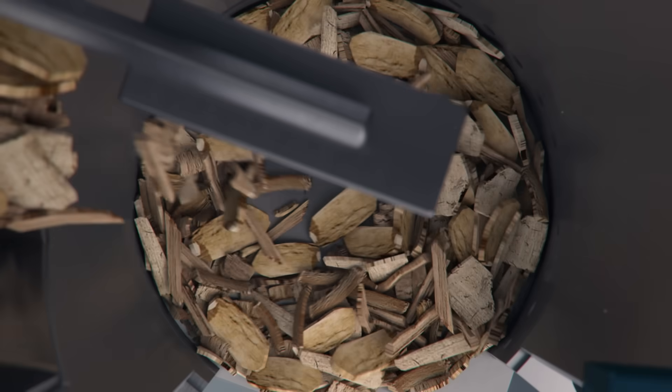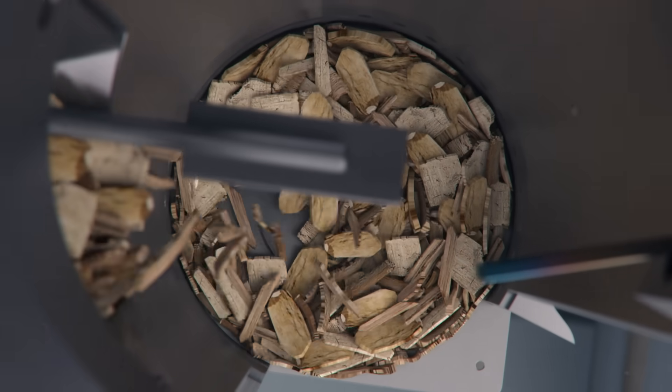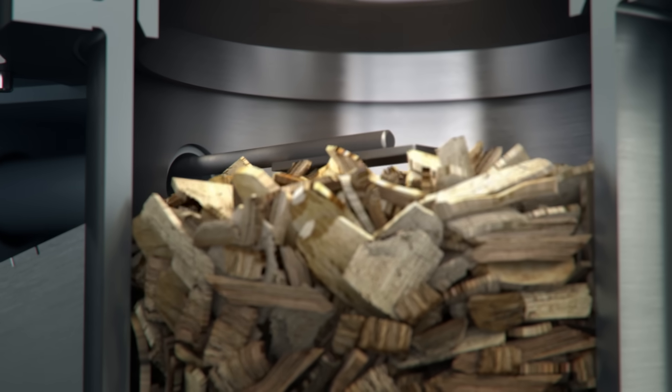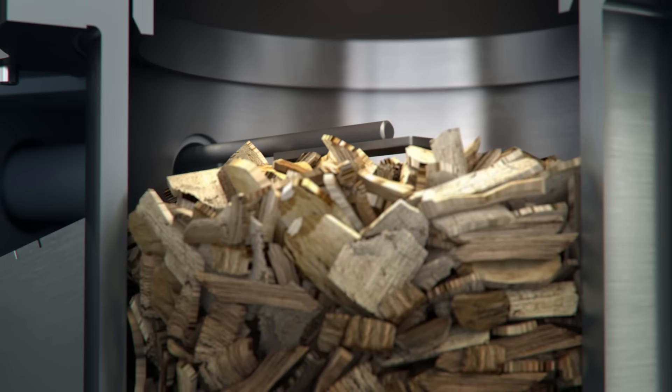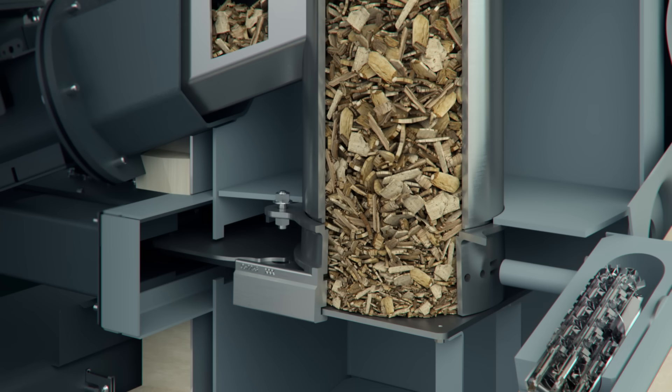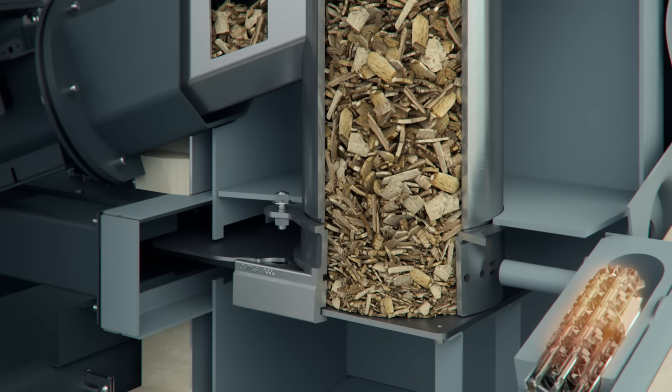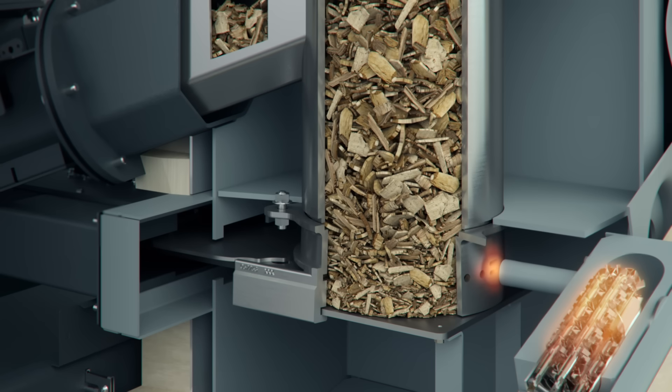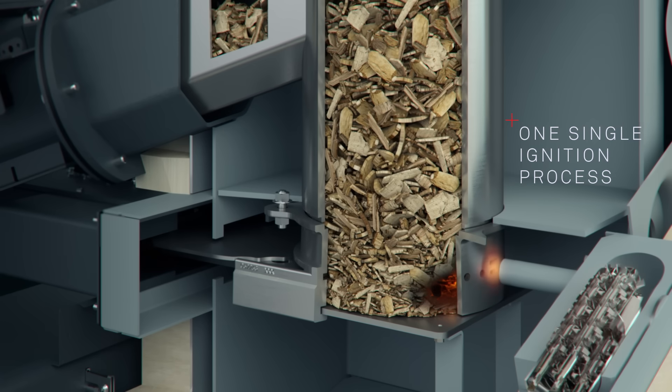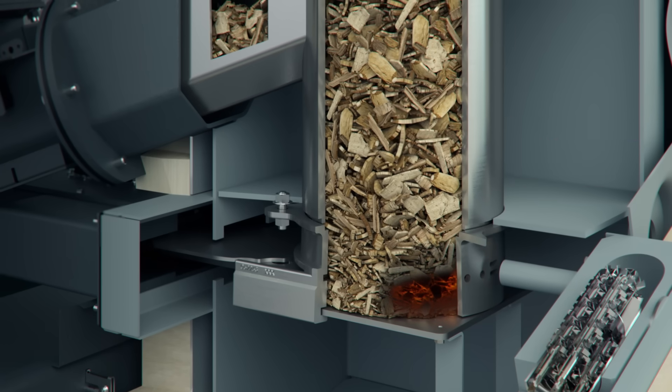Firstly, the complete combustion chamber is filled with wood chip. Supply of primary air and one single ignition process produces an ember bed in the bottom section. The heat of the ember bed carbonizes the wood chip above it.